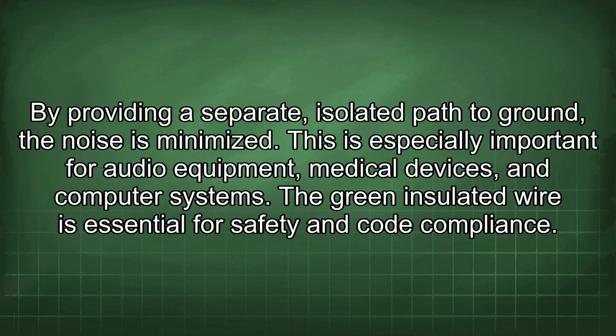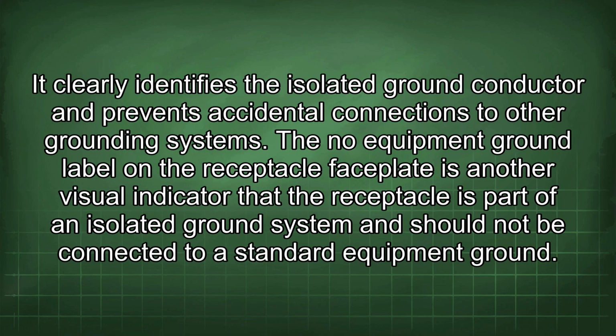The green insulated wire is essential for safety and code compliance. It clearly identifies the isolated ground conductor and prevents accidental connections to other grounding systems. The no equipment ground label on the receptacle faceplate is another visual indicator that the receptacle is part of an isolated ground system and should not be connected to the standard equipment ground.